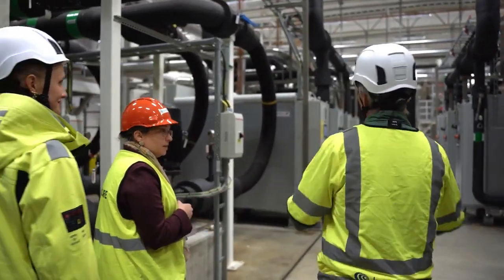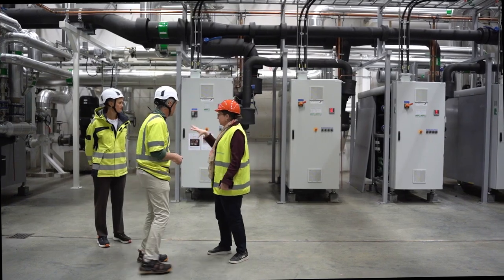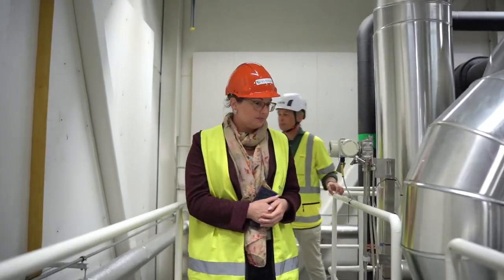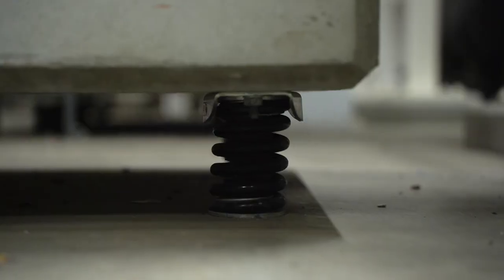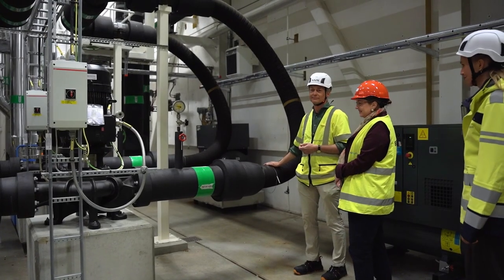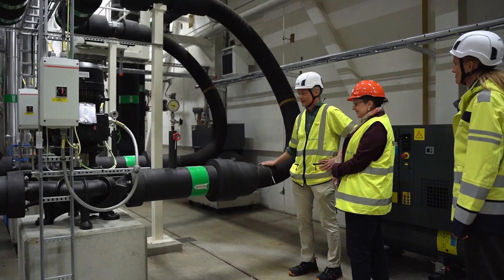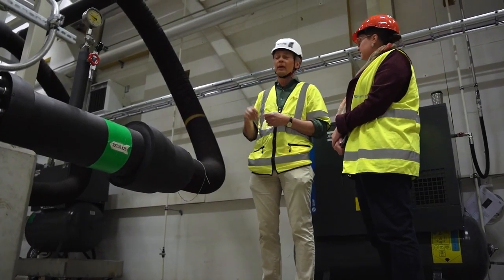Of course, Lund University always wants this facility to be in operation, so they have been very specific to us about what to install. One particular issue was that they were quite concerned about possible vibration problems. So we have installed, for example, springs below the distribution pumps, and we have installed flexible flanges instead of piping to ensure that we don't get any vibrations from our equipment to their research equipment.